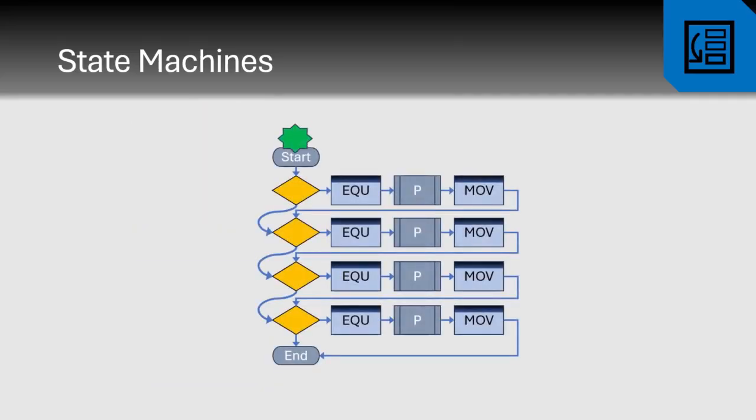This visualization best summarizes the behavior of state machines. One state is processed at a time and will not transition to another state until the next PLC scan. This method allows for recoverability with more advanced control if the state machine is interrupted. Due to the speed of the PLC scan time, the state machine can be configured to check multiple conditions one by one and respond quickly in real time. In reality, this visualization would occur at a much faster rate.